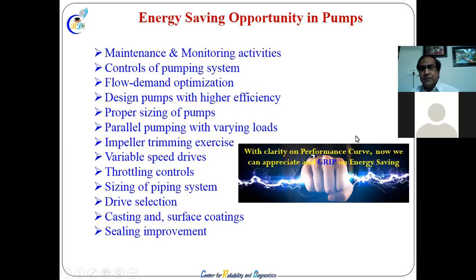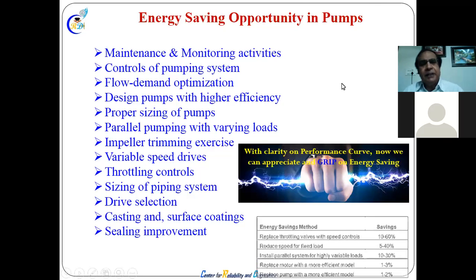With clarity on the performance curve, now we can appreciate and get a grip on energy saving. With no clarity on the performance curve, that means no clarity on scientific principles, meaning total disregard of all our scientific principles, and we cannot save energy by any means. No sir, they take care of that when we have taken a VFD. No, those people are much educated. Maybe somebody operating in the field is not so educated, he will run it his own way: control the valve, do this, do that. Even after taking a VFD, if you still change valves and use control valves for reduction, what is the point? So all the things come into the picture.